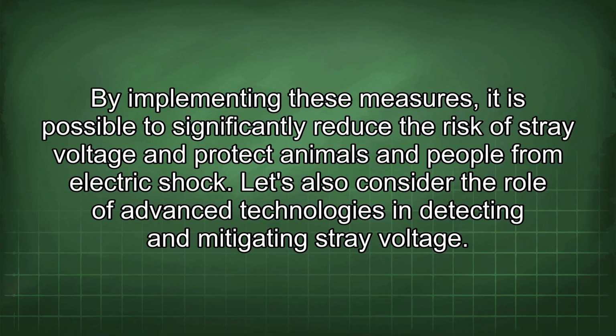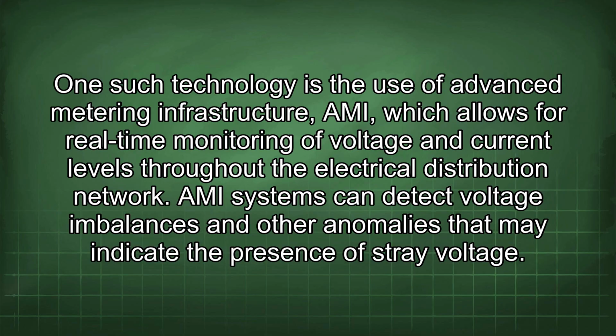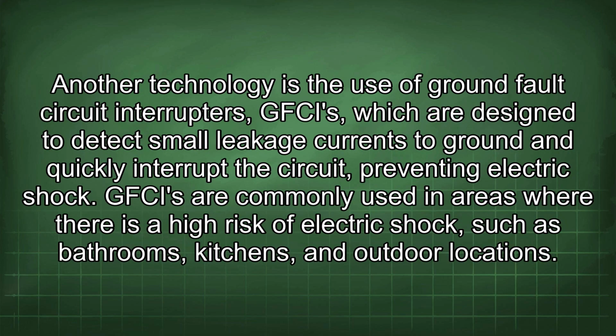from electric shock. Let's also consider the role of advanced technologies in detecting and mitigating stray voltage. One such technology is the use of advanced metering infrastructure, AMI, which allows for real-time monitoring of voltage and current levels throughout the electrical distribution network. AMI systems can detect voltage imbalances and other anomalies that may indicate the presence of stray voltage. Another technology is the use of ground fault circuit interrupters, GFCIs, which are designed to detect small leakage currents to ground and quickly interrupt the circuit, preventing electric shock.